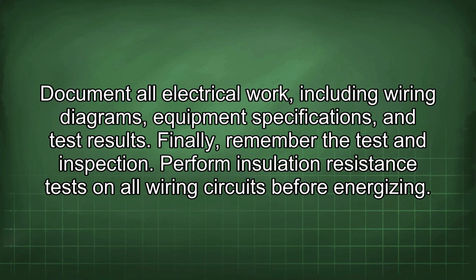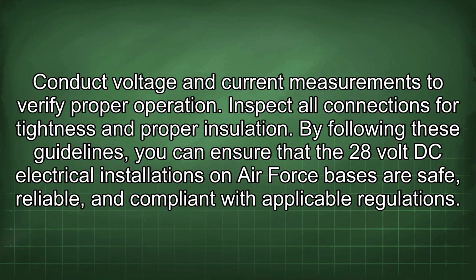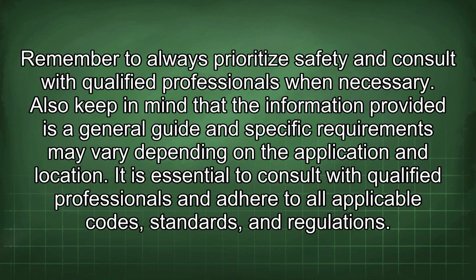Finally, remember the test and inspection. Perform insulation resistance tests on all wiring circuits before energizing. Conduct voltage and current measurements to verify proper operation. Inspect all connections for tightness and proper insulation. By following these guidelines, you can ensure that the 28-volt DC electrical installations on Air Force bases are safe, reliable, and compliant with applicable regulations. Remember to always prioritize safety and consult with qualified professionals when necessary. Also keep in mind that the information provided is a general guide and specific requirements may vary depending on the application and location. It is essential to consult with qualified professionals and adhere to all applicable codes, standards, and regulations.